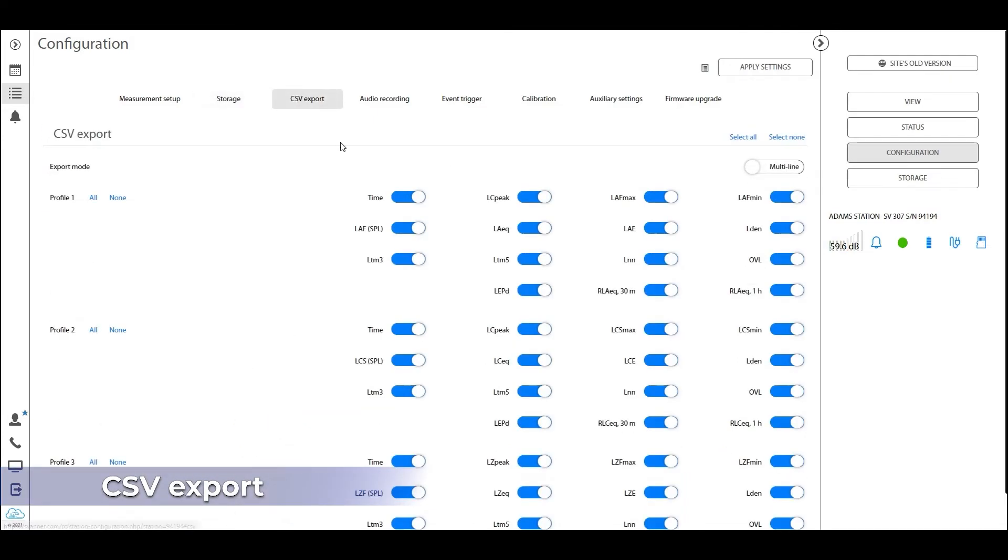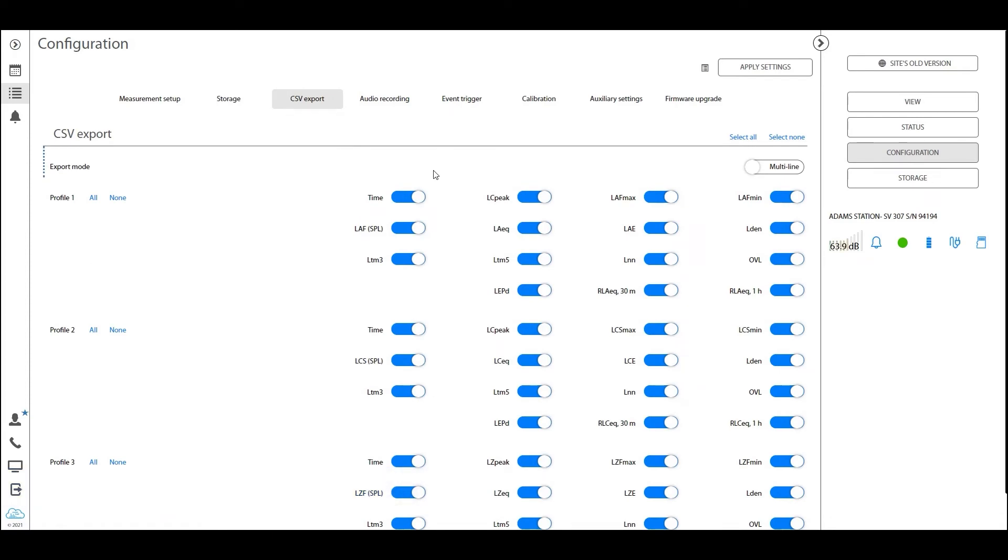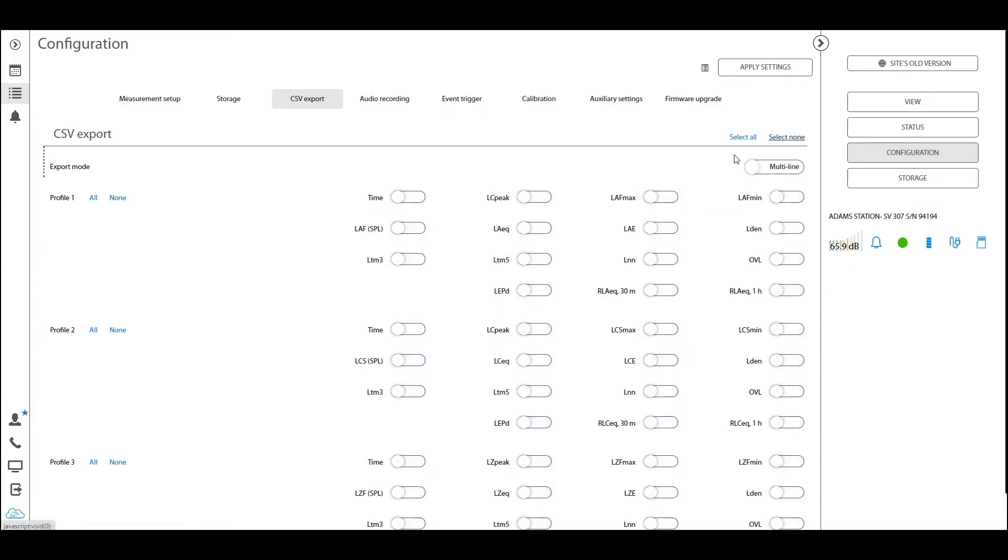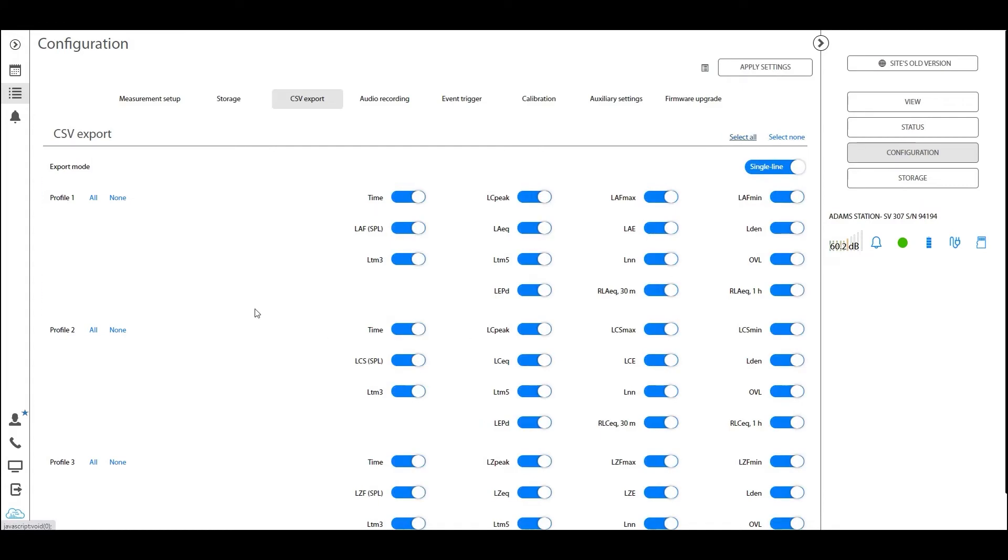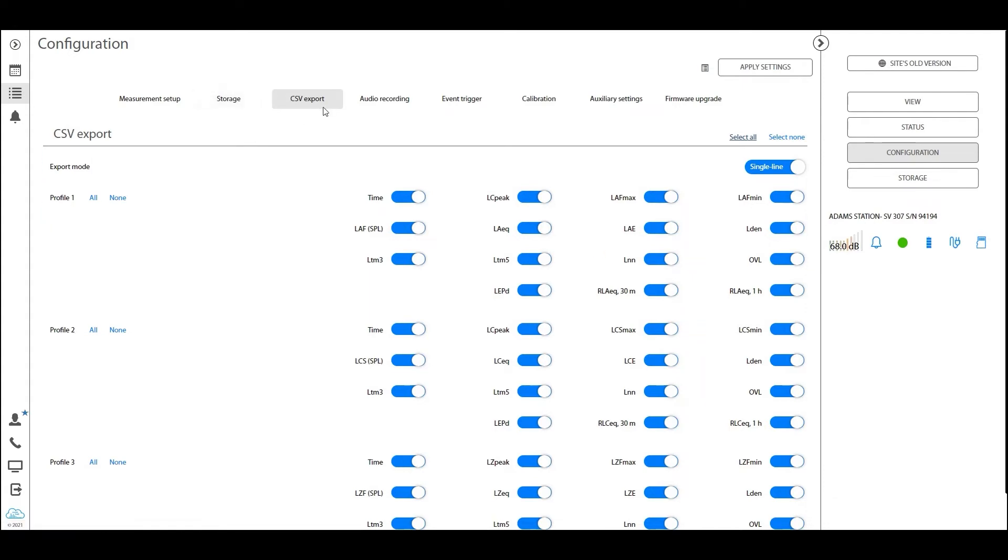The next tab is the CSV export tab. Here you can specify if you want to have a CSV file being exported with the logger file. So if you have all of this active, like right now everything is active, then it means that we will be generating two types of result files. One of the result files will be the logger data that we set up in the storage tab, and the other file will be the CSV export data.